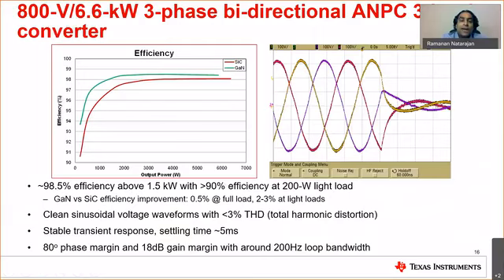A quick look comparing the efficiency between GaN and silicon carbide here shows that GaN is able to achieve over 98.5% efficiency with very clean, low distortion voltage waveforms, and able to get this high efficiency all the way down to about 1.5 kilowatts and over 90% efficiency at light load. GaN, because of its better switching capabilities at the same frequency, offers over 0.5% improvement in efficiency at full load and between 2 to 3% at light loads.